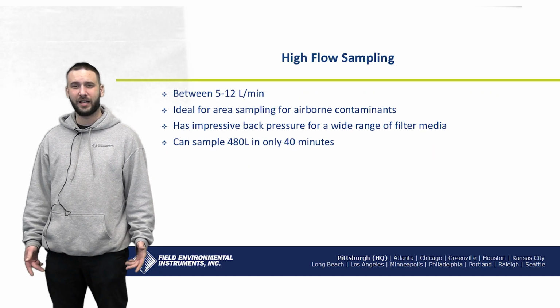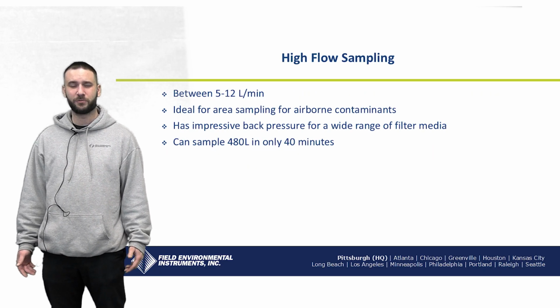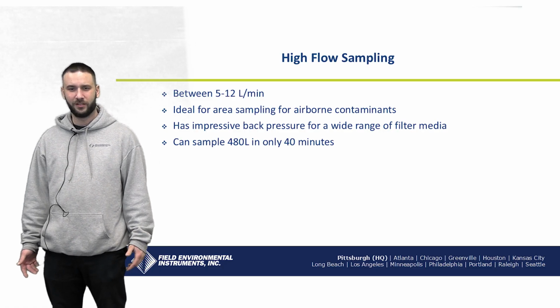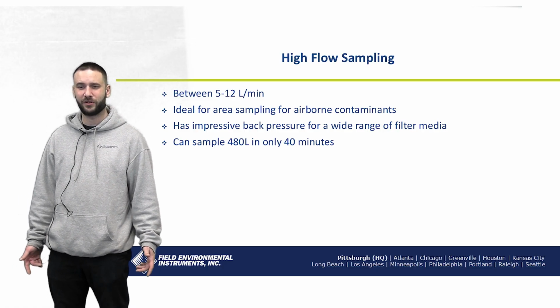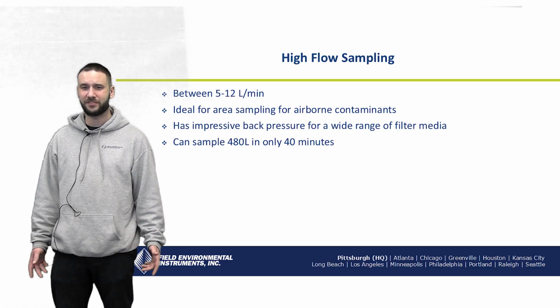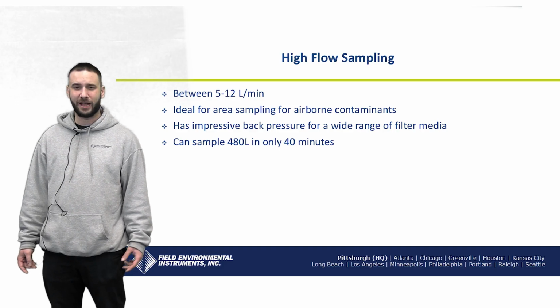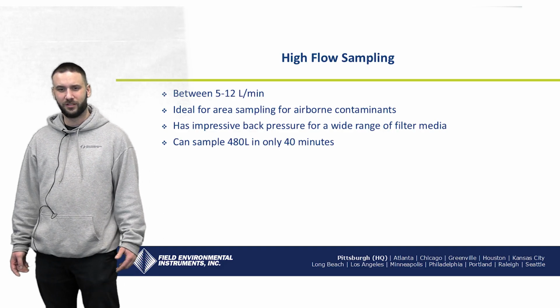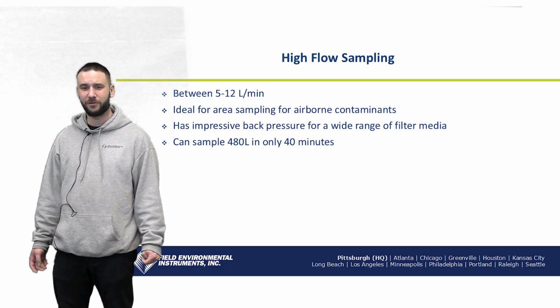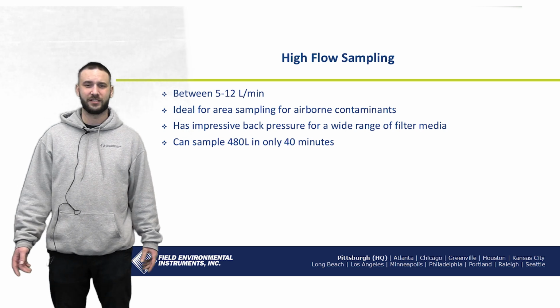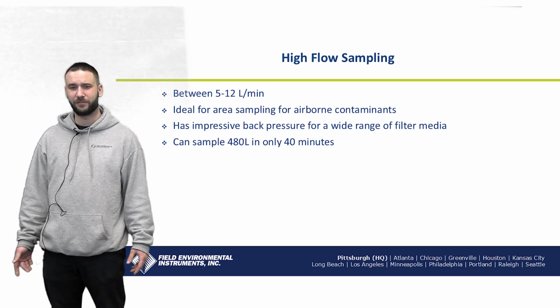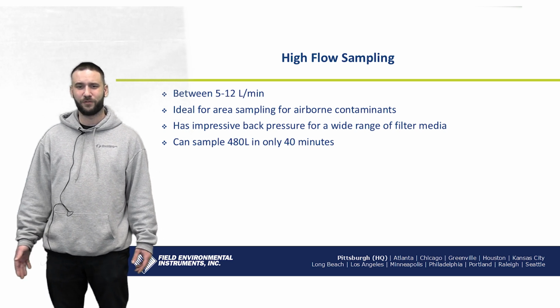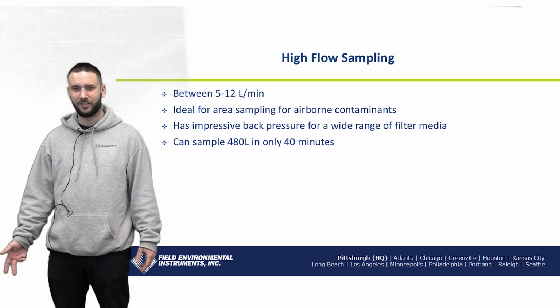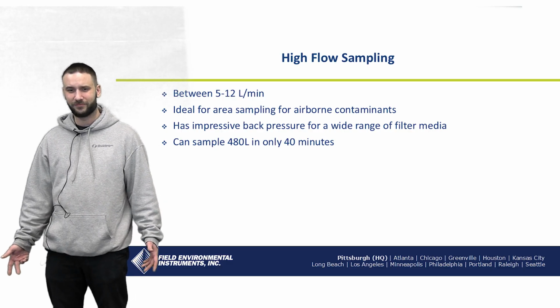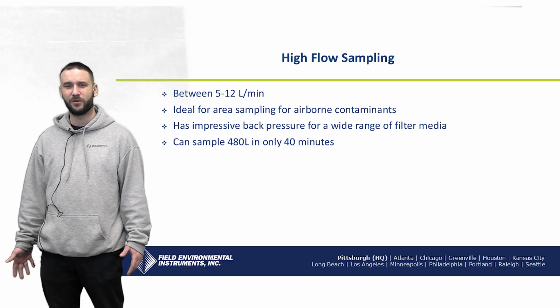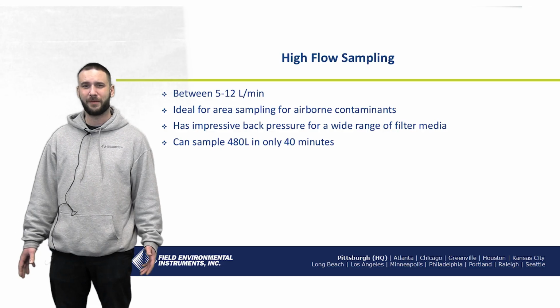Now, the Vortex is the high flow sampling pump, which runs between 5 to 12 liters per minute. It's ideal for area sampling for airborne contaminants like asbestos or any other hazardous material, and it runs well outdoors as well as indoors. It has impressive back pressure for a wide range of filter media, and it can sample 480 liters in only 40 minutes. If you divide that 480 divided by 40, you get 12. So it's very easy to determine what flow you want to set depending on how much time you have to sample.